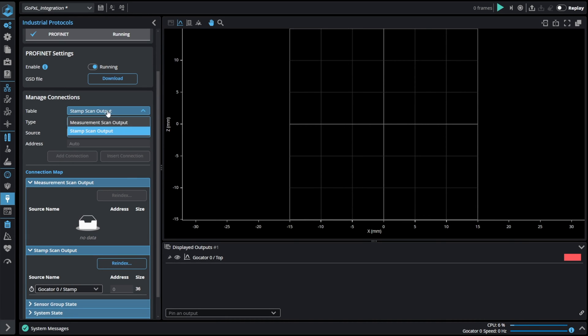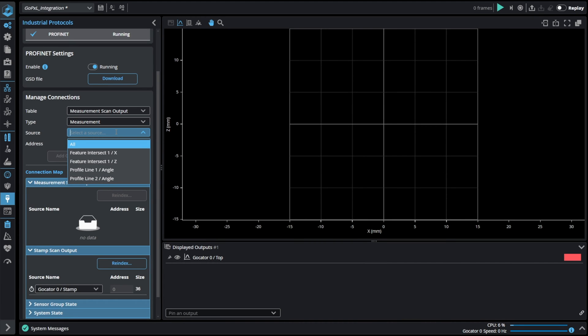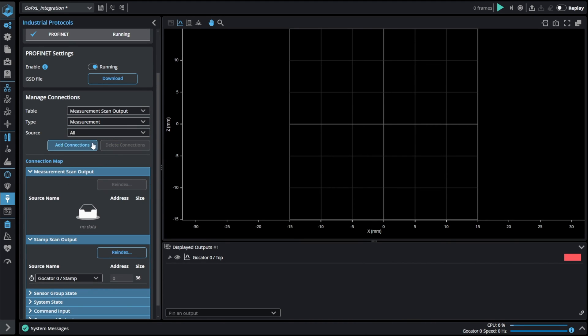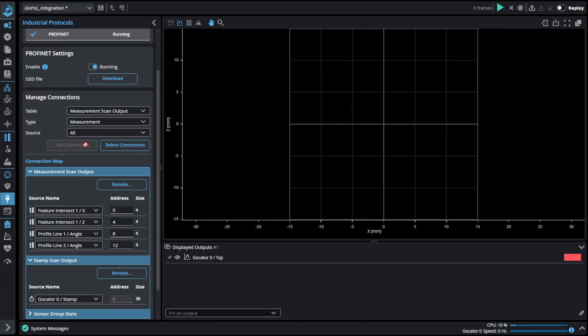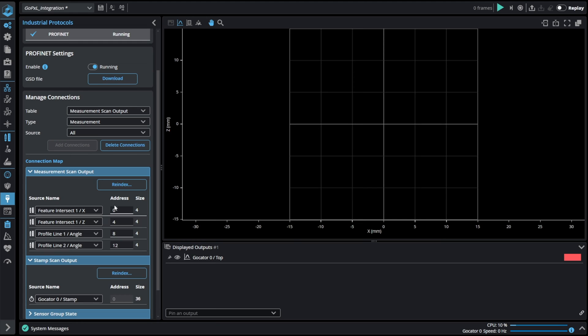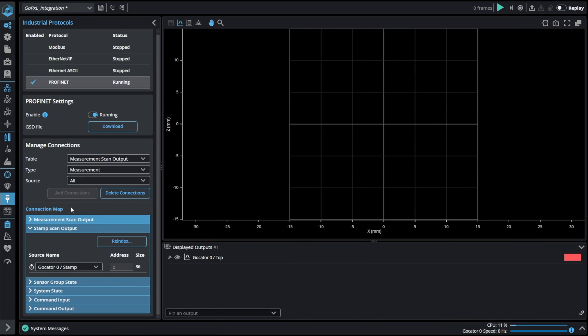When it comes to measurement results we can choose all and click on add connections. This functionality will add all of our inspection results to the measurement scan output automatically without the need of adding it one by one. All of the results have specified address and size. As you can see the result value has a size of 4 bytes.